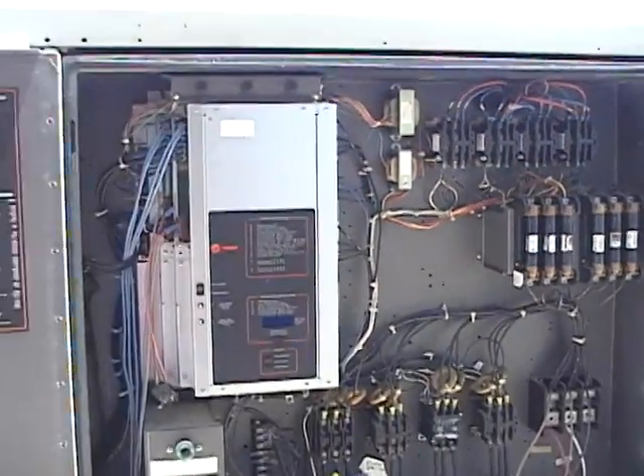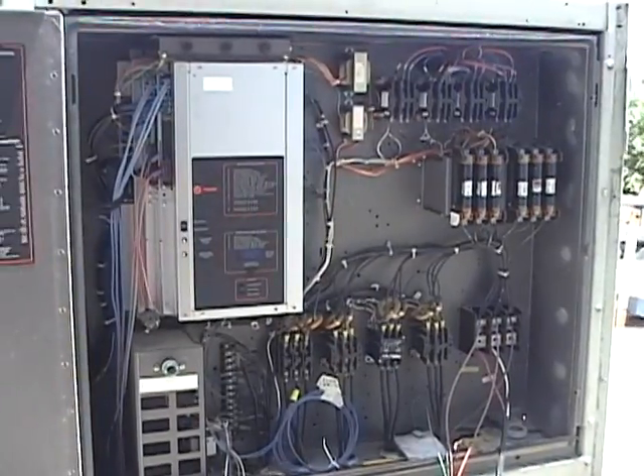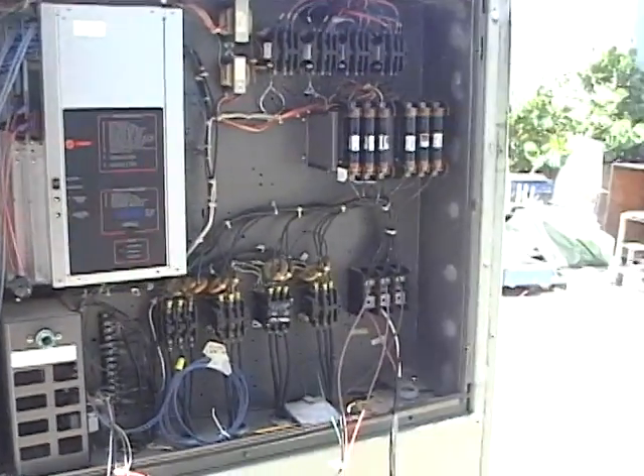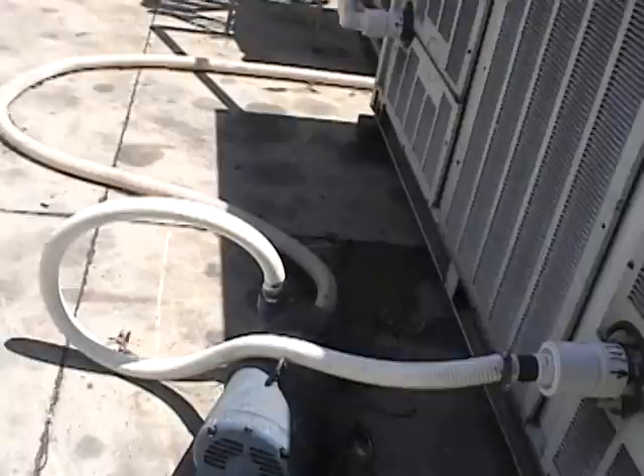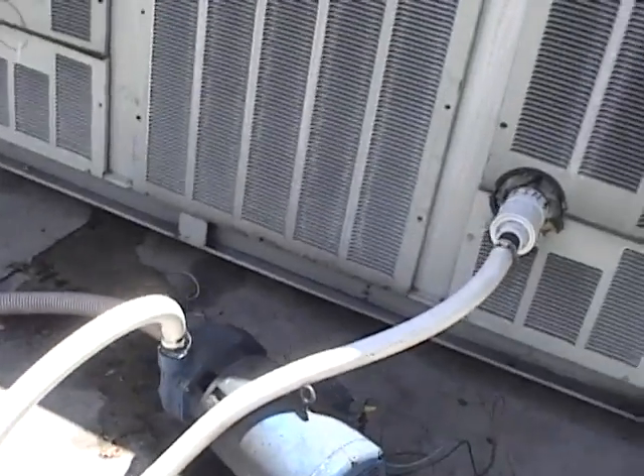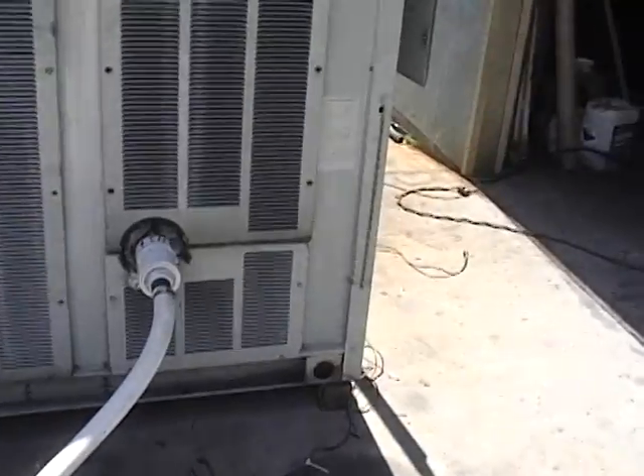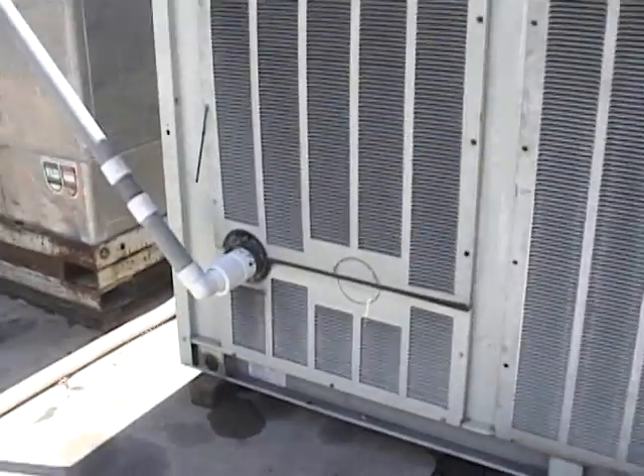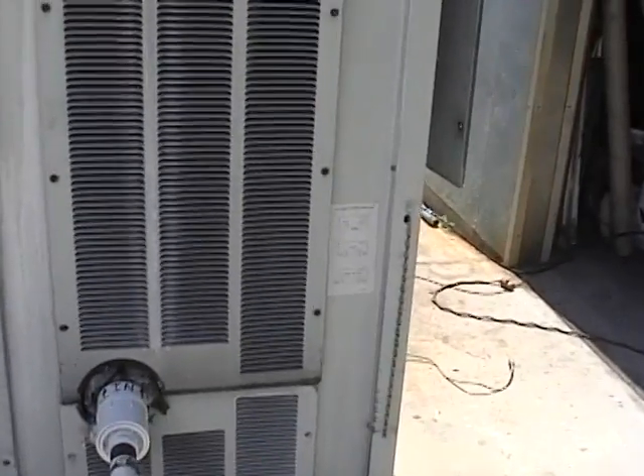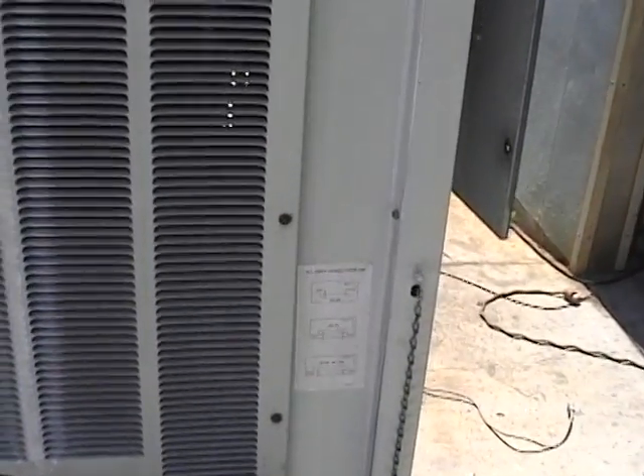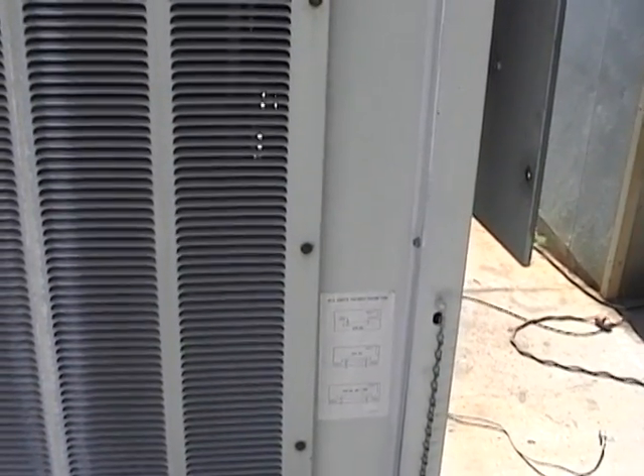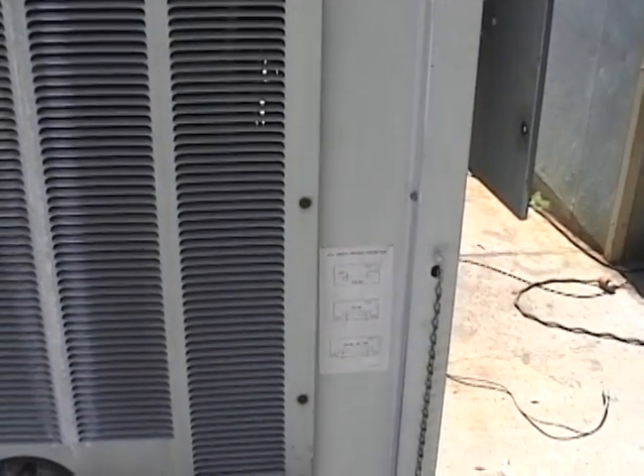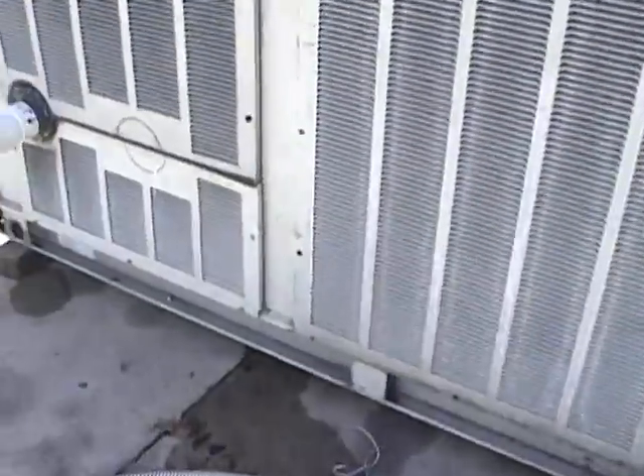I'm going to give you a quick overview around the outside of this unit, and then we're going to turn it on. We hooked 3 wires to a temporary pump in order to put water through the heat exchanger. I marked the in as in and the out as the out over here. Also, you'll notice there are some markings right over here that show you, based on the type of chiller, where the water should be going in and out. But we did mark them already in and out, and we have a 10 horsepower pump running on it.